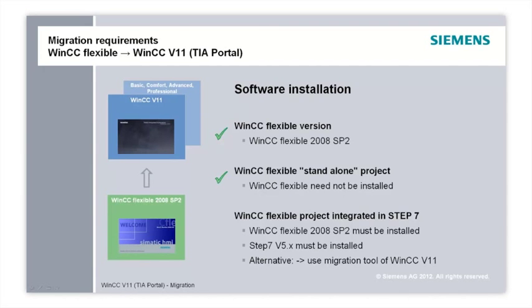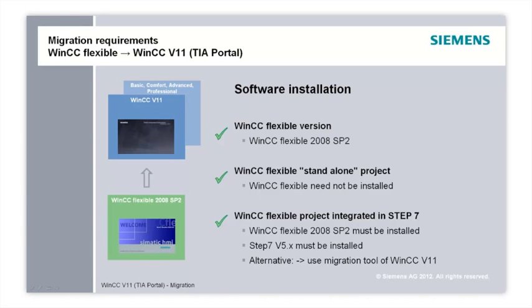When using a standalone project, WinCC flexible need not be installed on the computer for migrating the existing project to WinCC version 11. When using a WinCC flexible project integrated in Step 7, WinCC flexible and Step 7 must have been additionally installed on the computer in order to migrate the existing project to WinCC version 11. Alternatively, the migration tool can be used, which is available on the installation DVD of WinCC version 11 under Support.